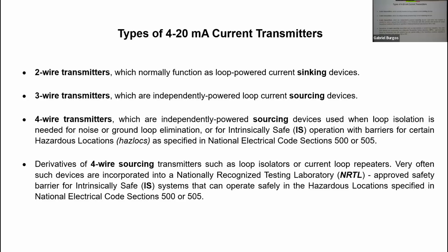Now, a 2-wire transmitter normally functions running from the energy already in the loop. It uses the current below the 4 milliamps, typically about 3.5 milliamps of current at some voltage, which is determined to some extent by what you have applied for.